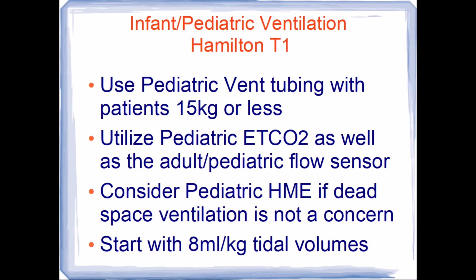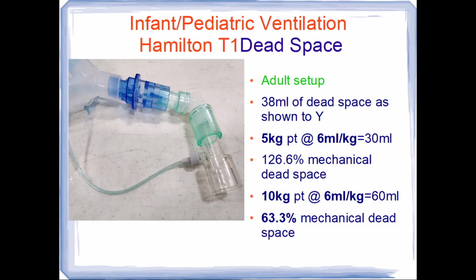We're going to consider the HME if dead space ventilation is not a concern, and you'll also see why here shortly. Any filters that you wish to place, the HEPA filters or anything else, place those on the ventilator at the expiratory valve. So the biggest difference between PEDS and adult is that we're going to start with 8 milliliter per kilo tidal volumes with kids. And we'll show you exactly why here.